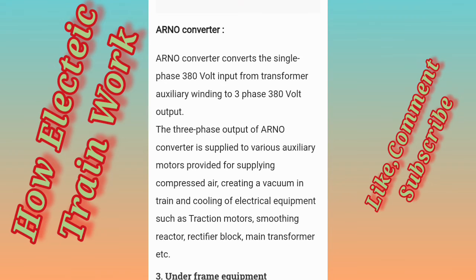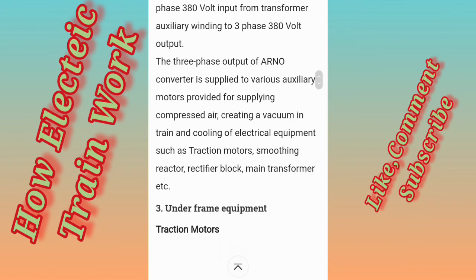The converter converts the single phase 380 volt input from the transformer auxiliary winding to three phase 380 volt output. The three phase output of the converter is supplied to various auxiliary motors provided for supplying compressed air, creating a vacuum in the train, and cooling of electrical equipment such as traction motors, smoothing reactor, rectifier block, main transformer, etc.